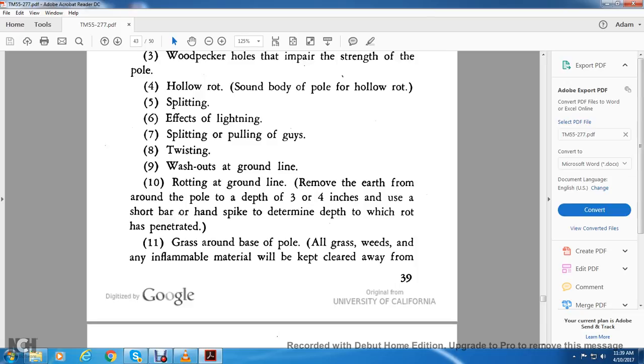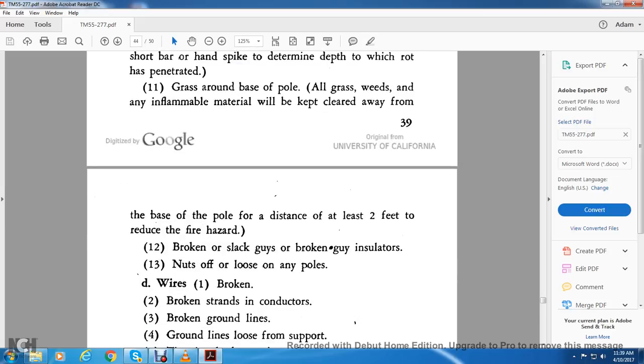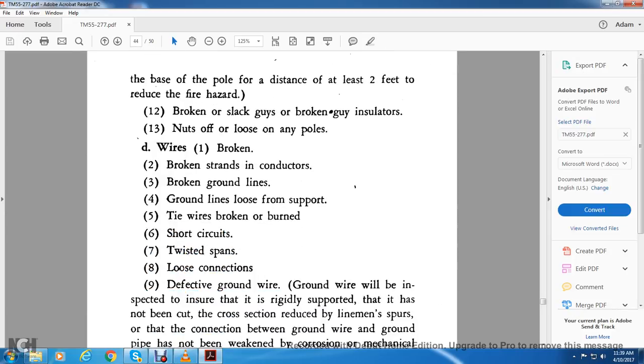11. Grass around the base of the poles. All grass, weeds, and other inflammable material will be kept cleared away from the base of the poles for a distance of not less than 2 feet, to reduce the fire hazard. 12. Broken or slack guys, broken guy insulators, and nuts off or loose on poles. D. The wires: broken strands in conductors, broken ground lines loose from supports, tie wires broken or burned, short circuits, twisted spans, loosened connections.